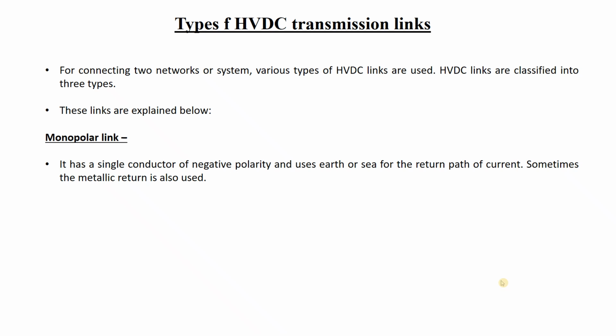For submarine or underwater transmission, often the sea is also used as a return path, while maintaining some precautions, and there are different techniques for that. Sometimes a metallic return is also used. That means not the actual soil, but metallic return paths in the ground, just like in railways. In electric traction also, metallic strips are connected to the tracks, which are used as the return path.